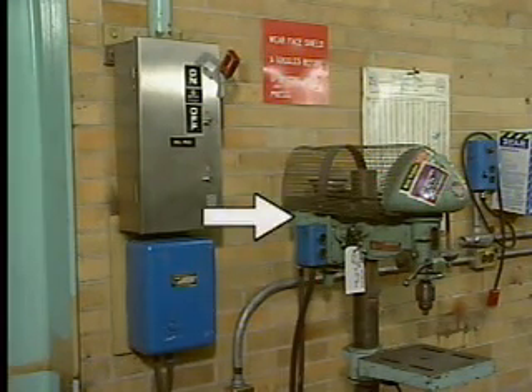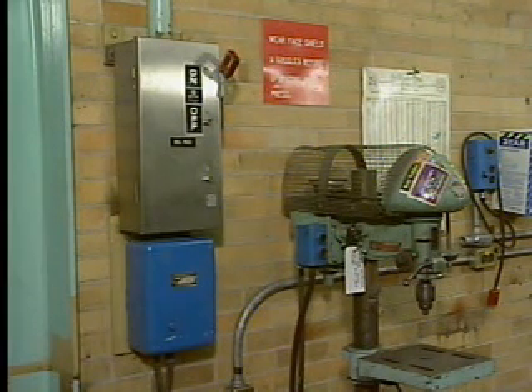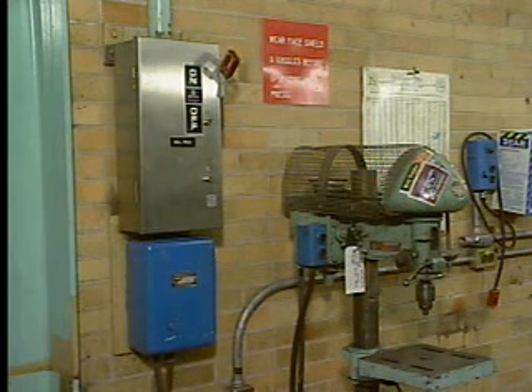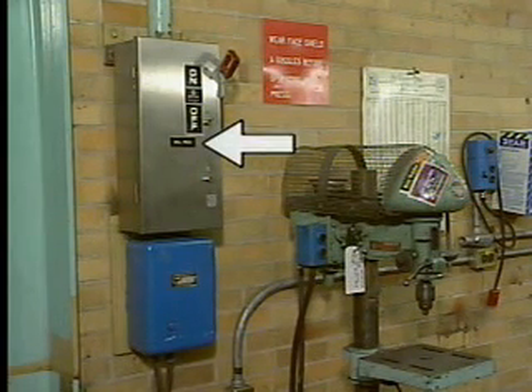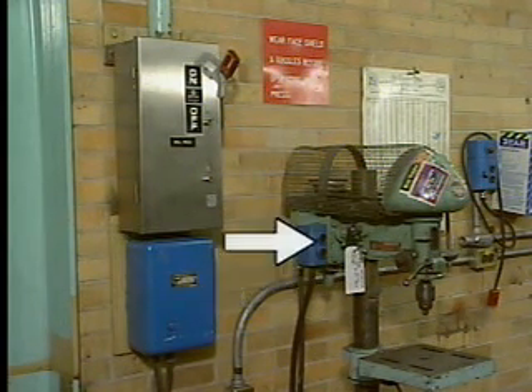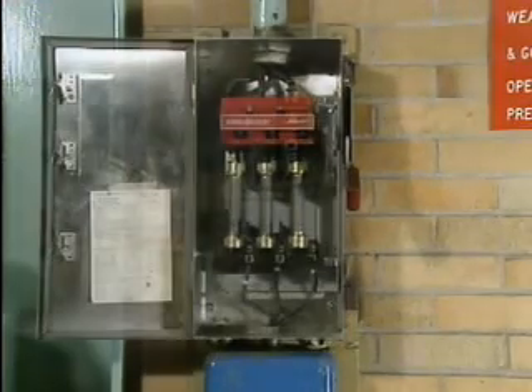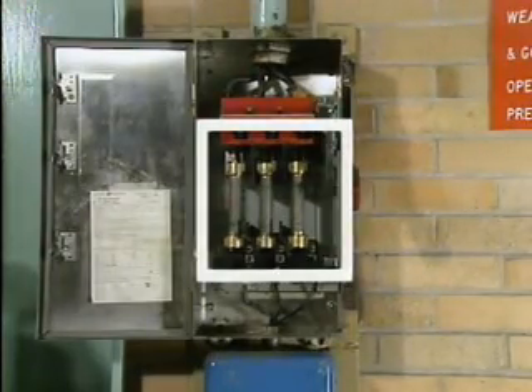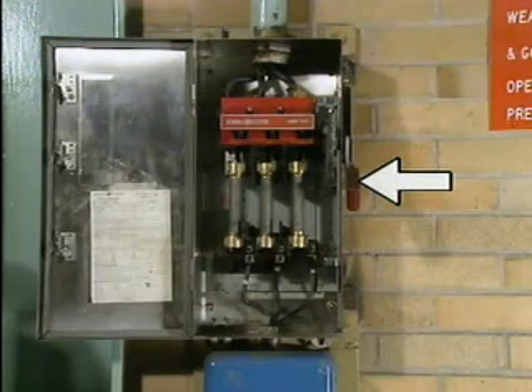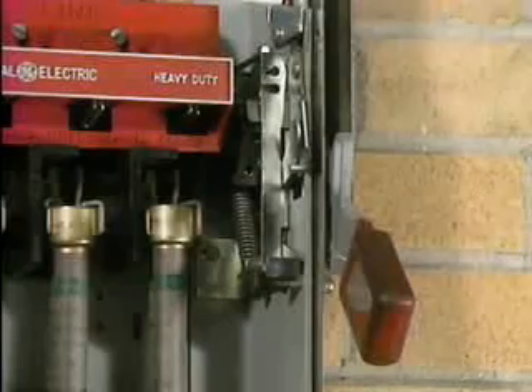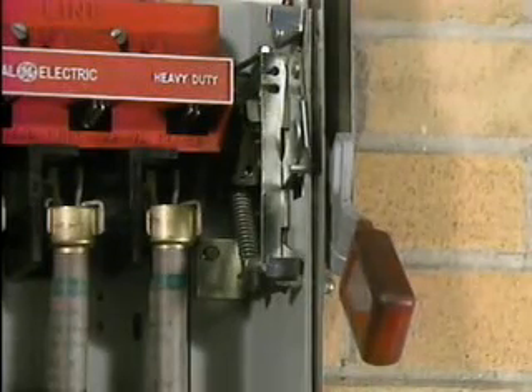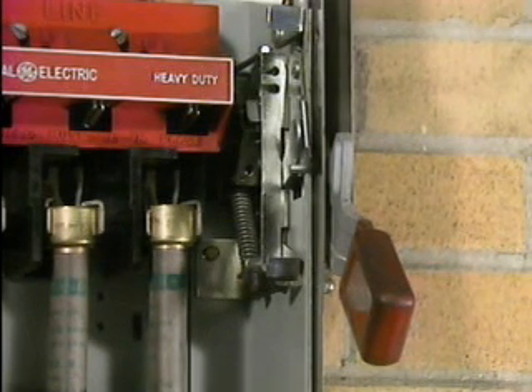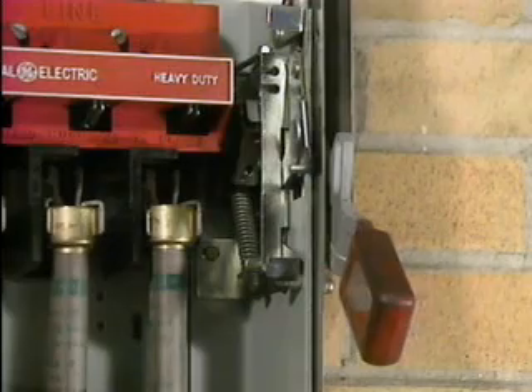It's powered by a 3-phase AC motor. The control circuit for the drill press contains components that are located in 3 separate enclosures: a fuse box, a control cabinet, and a push-button station. The fuse box contains 3 fuses and a power switch that has 3 knife blades. The fuse box door is interlocked with the power switch. This safety feature ensures that the fuse box cannot be energized while the door is open.